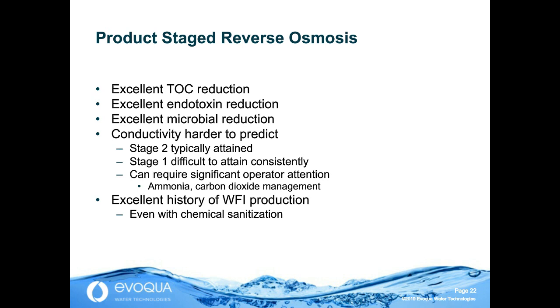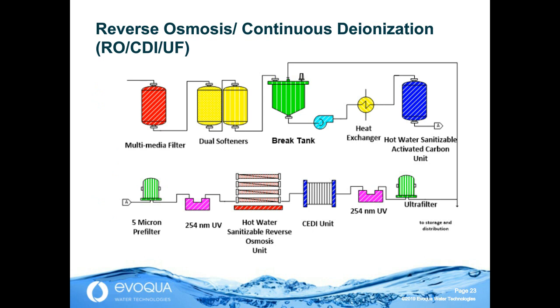Now, a very common configuration now is a single pass of reverse osmosis, continuous deionization, and a final ultrafilter. So here again, it could be softener or antiscalant. We talked about the methods of dechlorination. There's almost always filtration upstream of RO, possibly UV, but the real working units are a hot water sanitizable RO, continuous deionization, and ultrafiltration. There are many of these systems out for highly purified water. There are some out for WFI, and we'll talk about some case studies. So this is a very popular configuration.